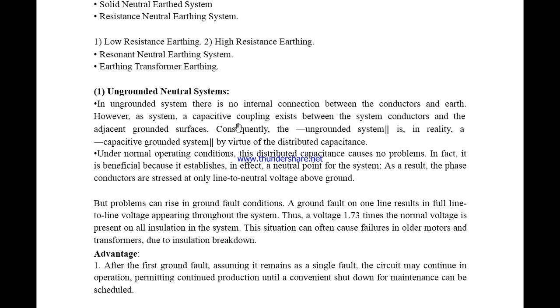The methods of neutral grounding are the unearthed neutral system, solid grounding, resistance grounding, resonance grounding, and earthing transformer, etc. For example, let us consider an ungrounded system. In this ungrounded system, there is no internal connection between the conductors and the earth. However, the impact of capacitive coupling may be there, since the conductor and earth are at different potentials. Under normal conditions, this distributed capacitance will cause no problem. In fact, it is almost beneficial to the neutral point.